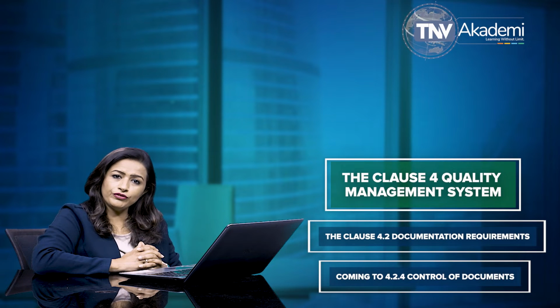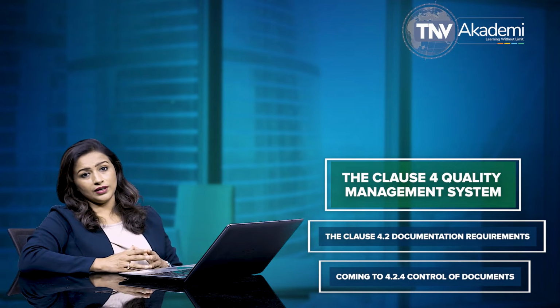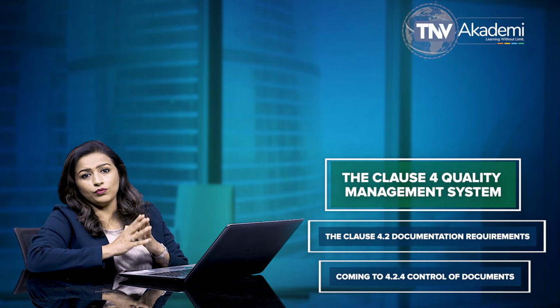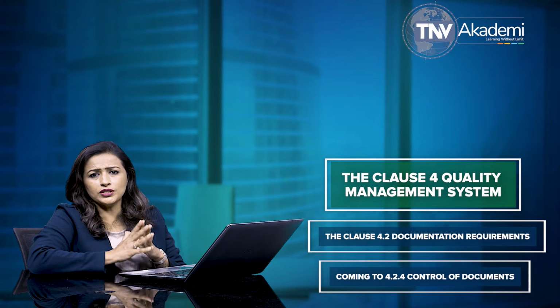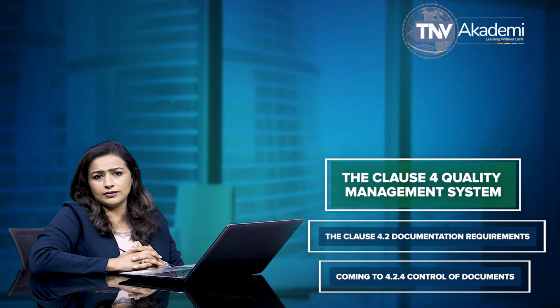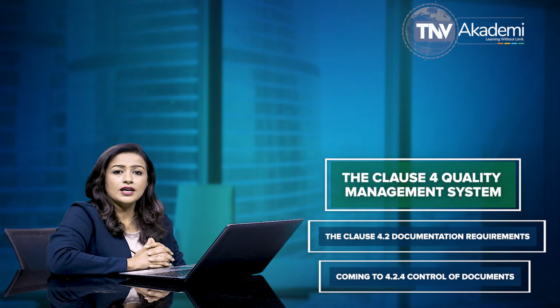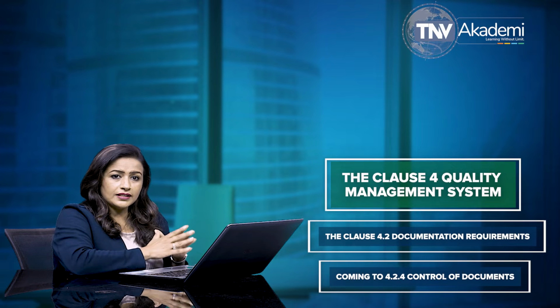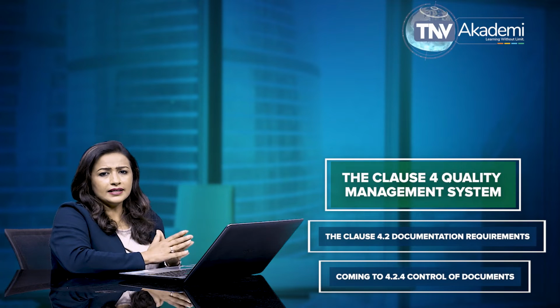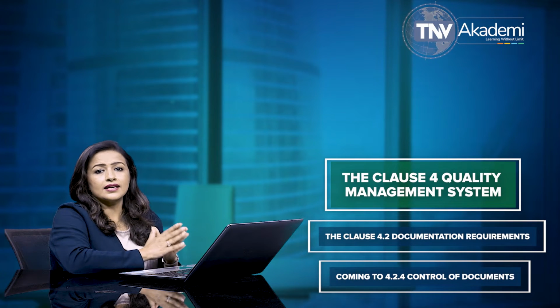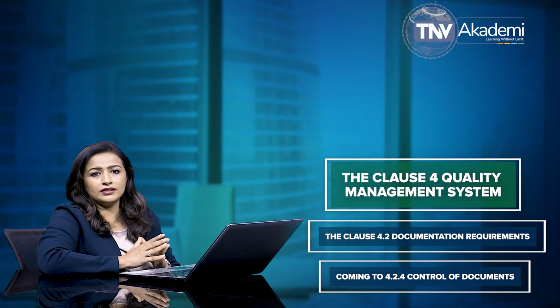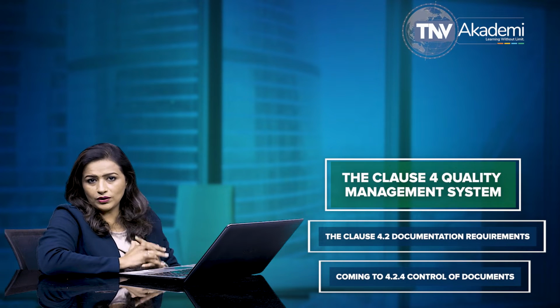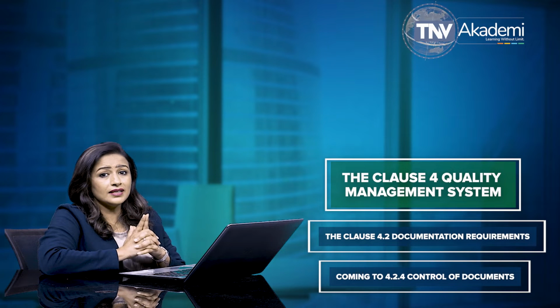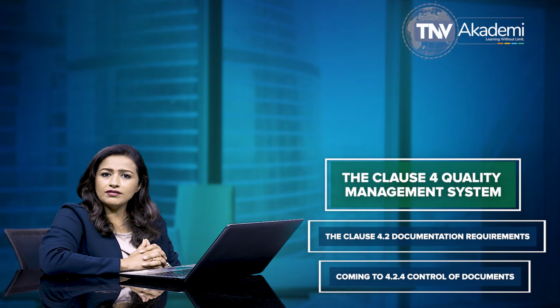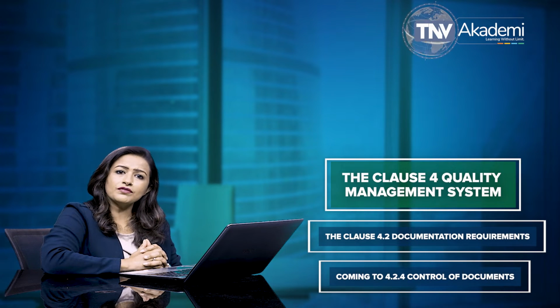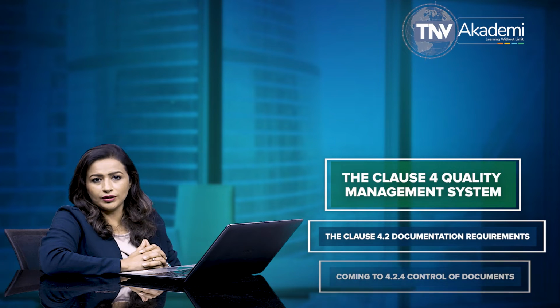Clause 4.2.4 says that the organization is required to define the period for which at least one copy of obsolete documents shall be retained. This period must ensure that documents to which medical devices have been manufactured and tested are available for at least the lifetime of the medical device as defined by the organization, but not less than the retention period of any resulting record, or as specified by applicable regulatory requirements.